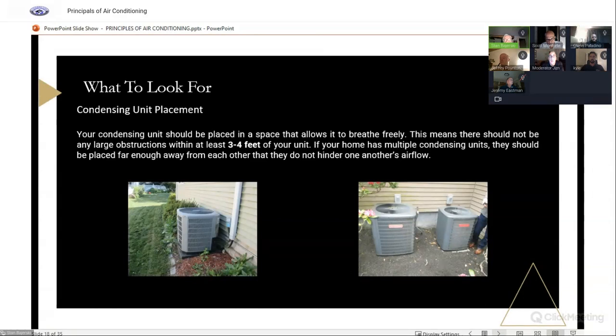Jim, back to keeping that off the ground. I don't know how many you see that are on the ground, but a lot of them aren't on pads, right? They're just sitting right on the ground. Right. Let's talk about clearance of the units for now. Usually you're recommended to have 3 to 4 feet of clear space around the unit. That would include shrubbery, fencing. A lot of people try to put these privacy fences around there because they don't want people to see the ugly condensing unit. Just like if the coil gets dirty and we're not getting proper airflow, you can have a clean coil but still be cutting down the airflow on that condensing unit. So shrubbery should be trimmed back.